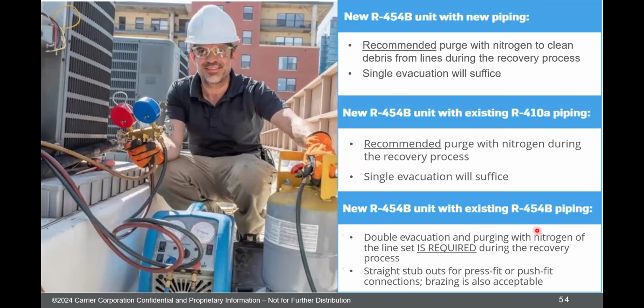If they have existing R454B or R32 piping, so they have an existing flammable refrigerant inside the pipe, that is the only time you're required to do double. So you're going to purge and evac, and then purge and evac again. You're going to do it twice. I don't know why. Maybe they just figure you didn't do a good job the first time. Do it a second time before you open the pipe up, right? So in any case, that's the case there. Questions on that?